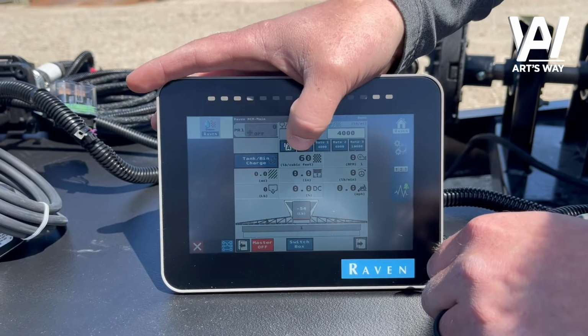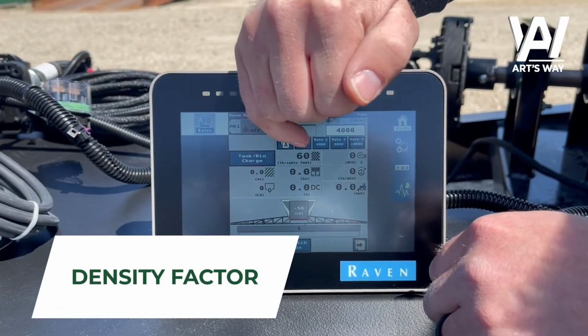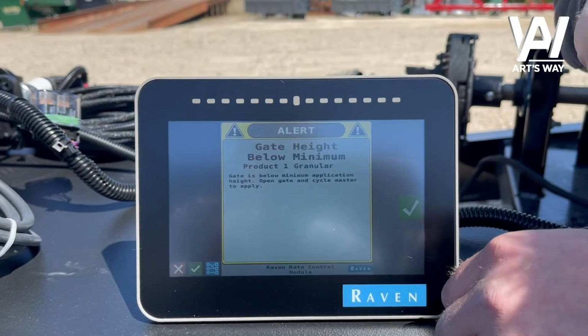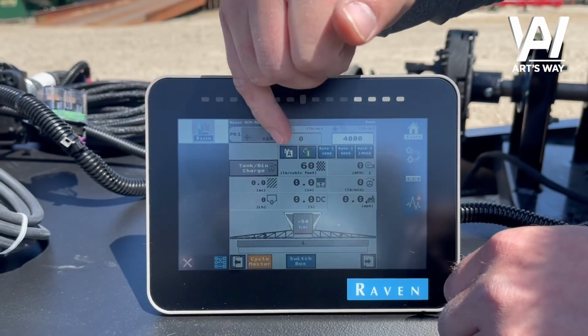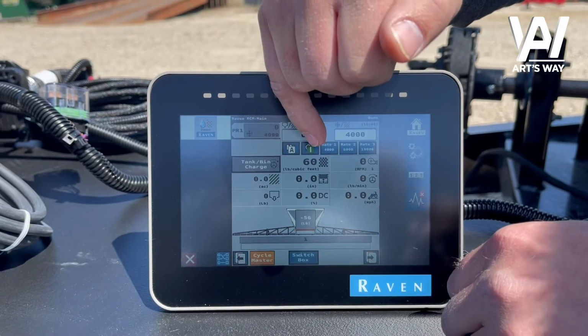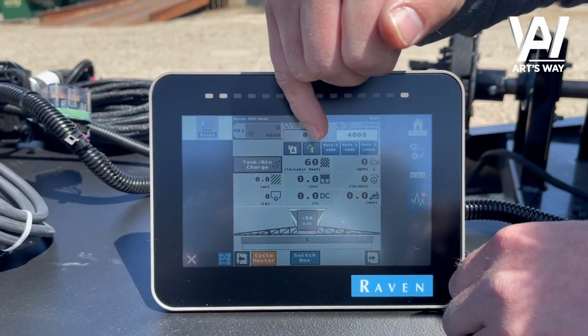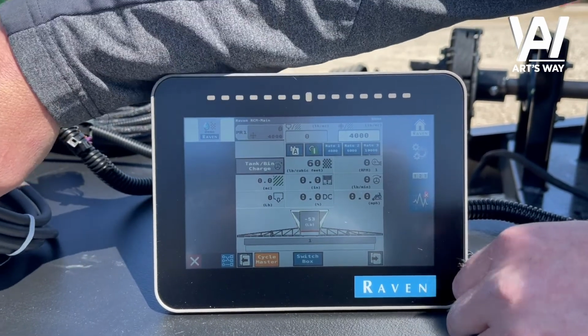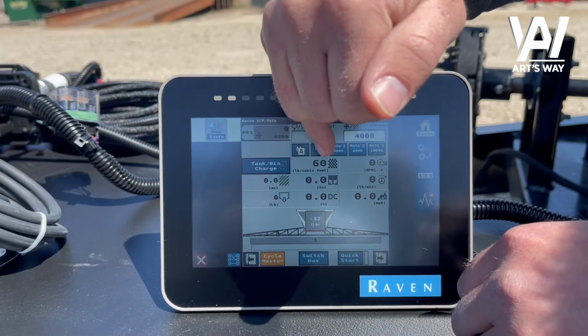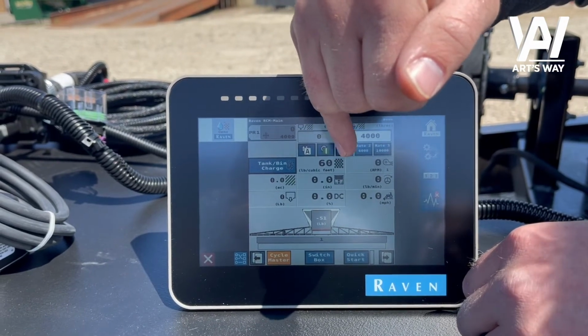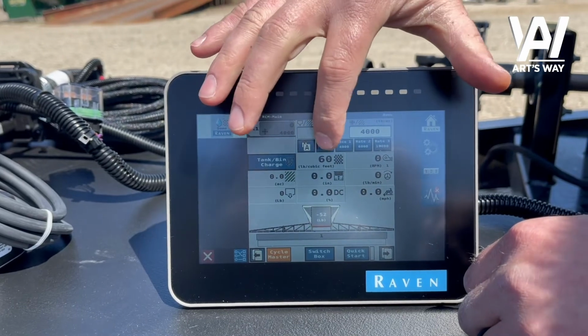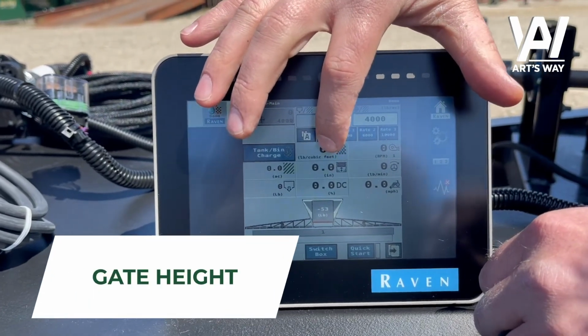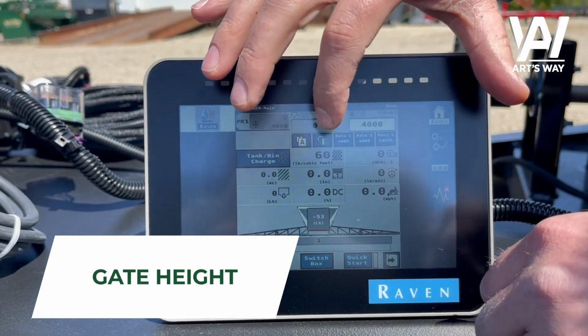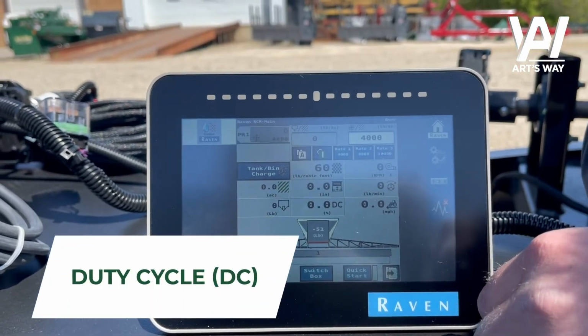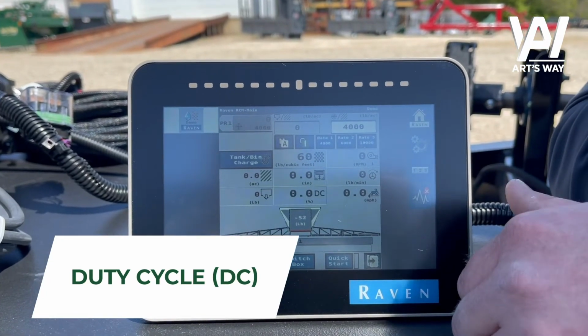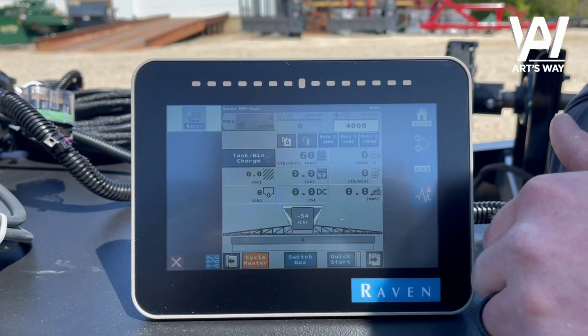The other one here you'll see is your density factor reading right here in the center. So we have it set at 60 currently. Once the system is running and starts adjusting the density value for the dynamic cal, you'll notice that value will jump around as the system adjusts. The one right below that is your gate height reading, and we'll touch on the calibration shortly. The one below that has our duty cycle, or DC, and that's the amount of effort that we're sending to the control valve to move the belt.